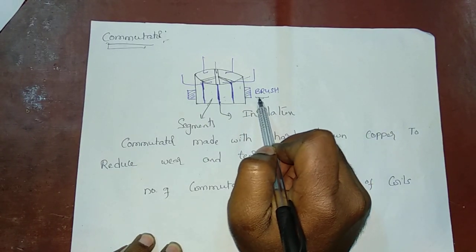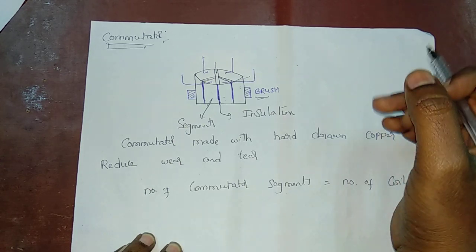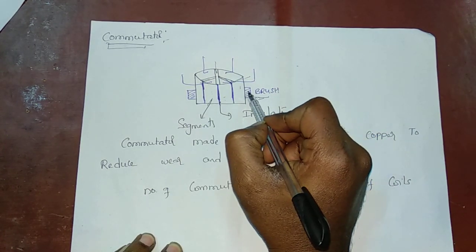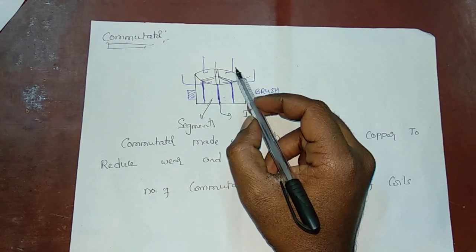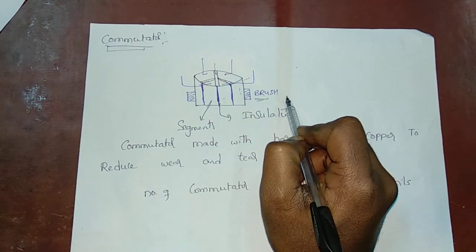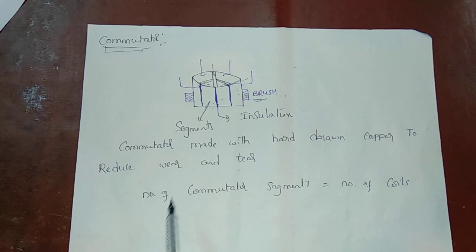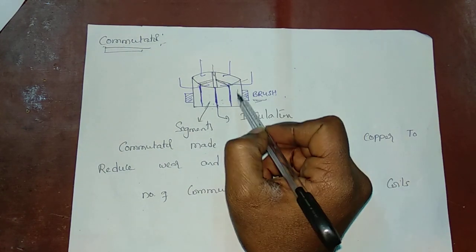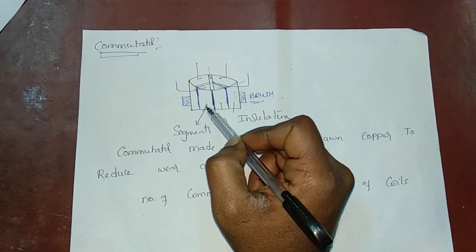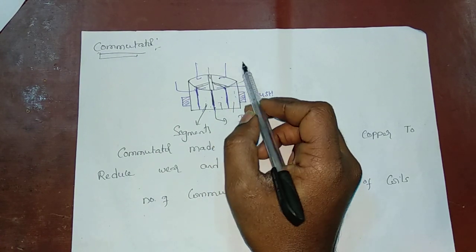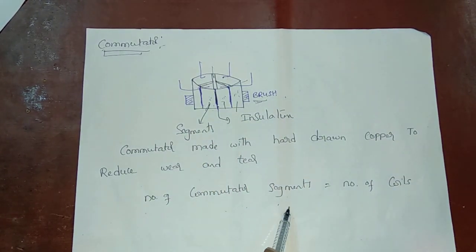This is where the commutator comes in. The commutator converts AC to DC. We connect the armature conductors through brushes to the commutator. The commutator segments are insulated from each other. The number of commutator segments equals the number of coils — every coil is connected to one commutator segment. For example, if there are 220 coils, there are 220 segments.